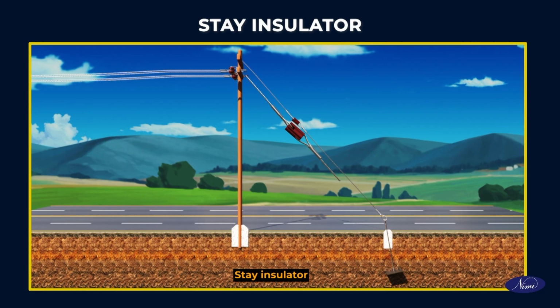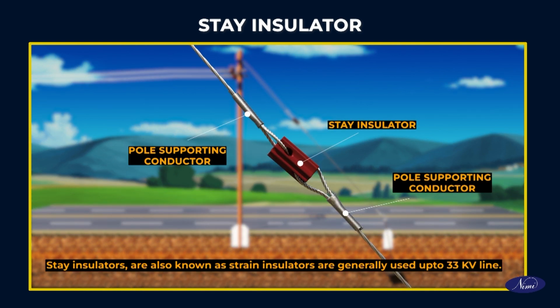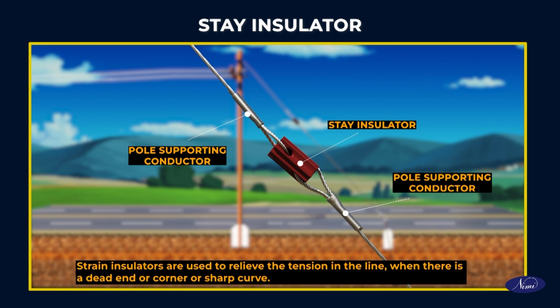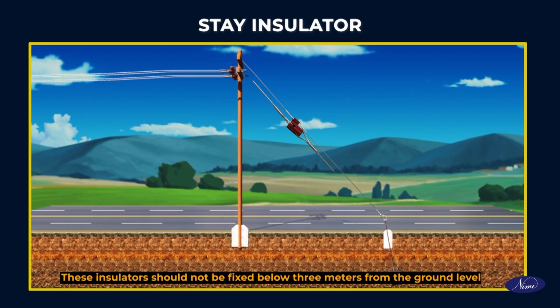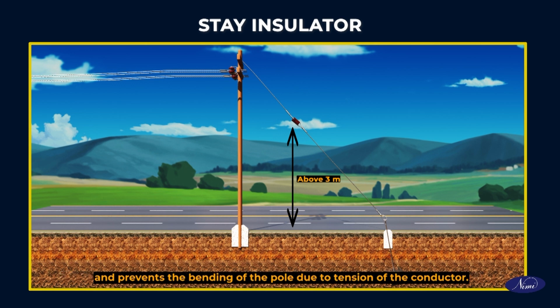Stay insulator. Stay insulators are also known as strain insulators and are generally used up to 33 kV line. Strain insulators are used to relieve the tension in the line when there is a dead end or corner or sharp curve. These insulators should not be fixed below 3 meter from the ground level and prevent the bending of the pole due to tension of the conductor.